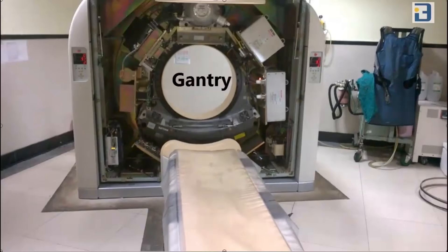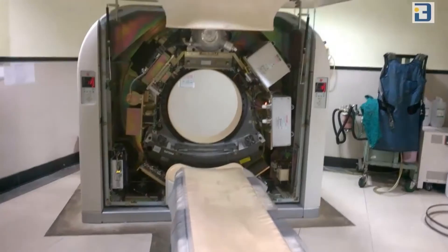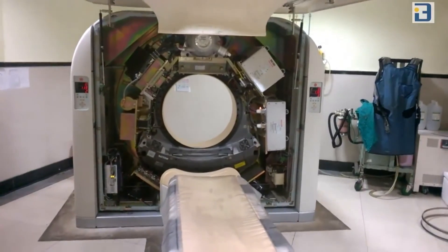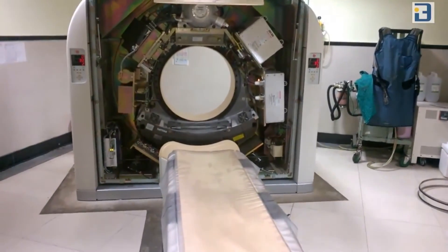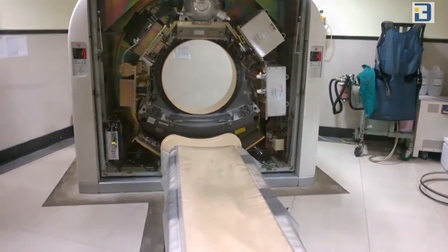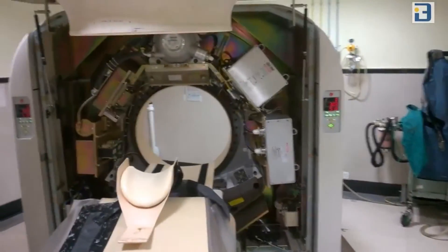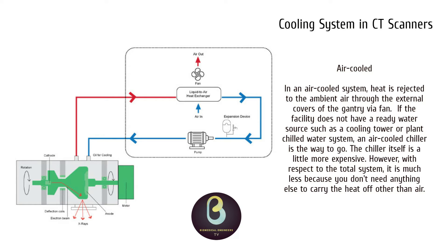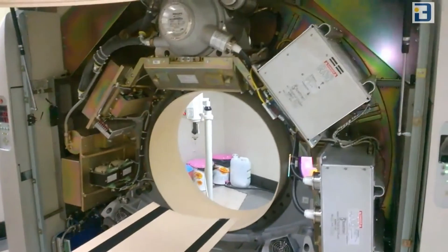The fourth component is the cooling system. Cooling mechanisms are included in the gantry and can take many different forms, such as blowers, filters, or devices that perform oil-to-air heat exchange. Cooling mechanisms are important because many components can be affected by temperature fluctuations.